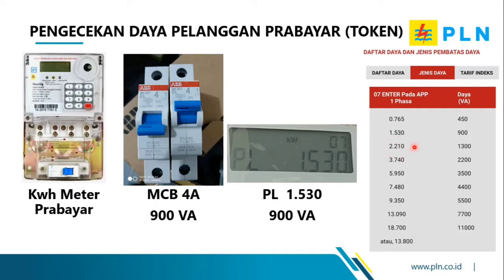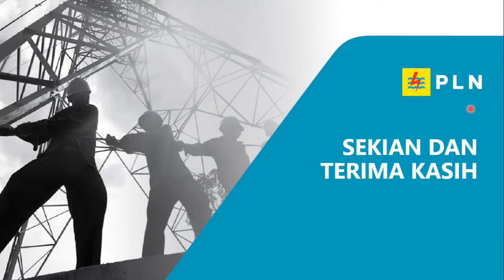Ada beberapa KWH meter yang menampilkan tiga angka di belakang koma, misalnya 1.530, namun ada juga yang hanya dua angka di belakang koma, yaitu 1.53. PL di sini adalah power limit — artinya pembatas daya. Teman-teman atau elektrisan bisa mencoba pada meter prabayar dengan menekan 07 enter, kemudian bandingkan angka yang muncul di layar dengan tabel yang ada di aplikasi panduan APP prabayar.